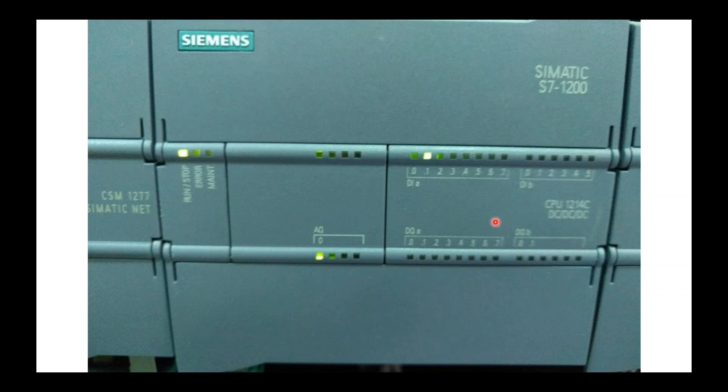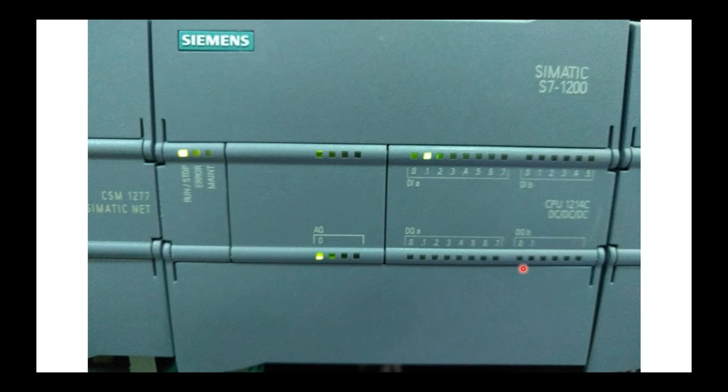Now you may also see AC here. You also might see something called relay. Relay allows you to be dealer's choice, so to speak. If you want to run half your inputs as AC, you can. If you want to run your other half as DC, you can. If you want to run 24 volt AC outputs and then 120 volt AC outputs, you could. It will clearly denote like four bits of one set of relay contacts and another four bits of another type of relay contacts if this says RLY. So be wary of that as you're running.